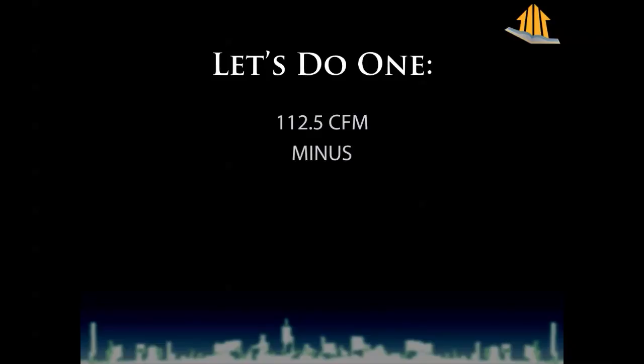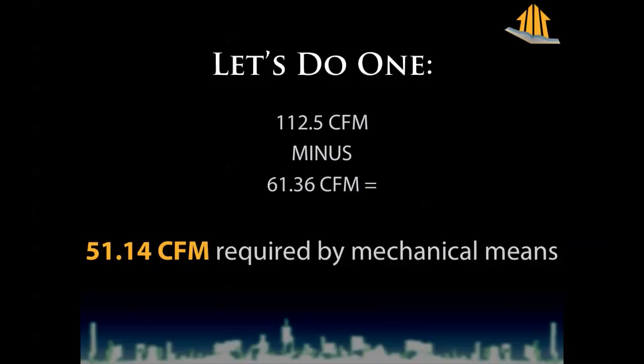Then I subtract the air infiltration credit of 61.36 CFM, and I get 51.14, which really is 52 CFM that I would need to install because I can't find a fan that's going to be 51.14. So I would install 52 CFM at least in that house to ventilate it mechanically 24 hours a day.